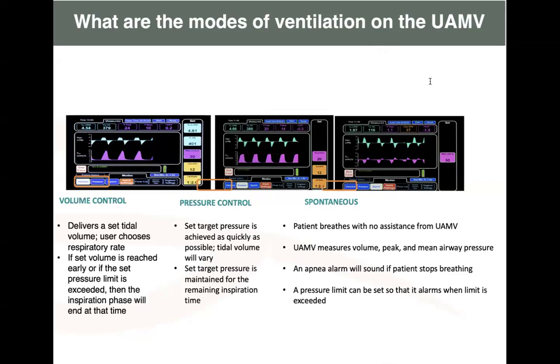I know the majority of our anesthetists, when they take a patient from volume control or pressure control, go straight to putting off the vent and continue ventilating without looking at the vent. But it's like ignoring that the vent has got a spontaneous mode, whereby we can still manually bag the patient, or the patient can be on the spontaneous mode, but also the vent can give you parameters, because when you're on the spontaneous mode, the UAMV will still give you numbers on how adequate the patient is ventilating.